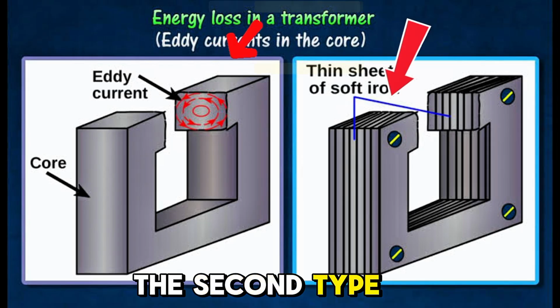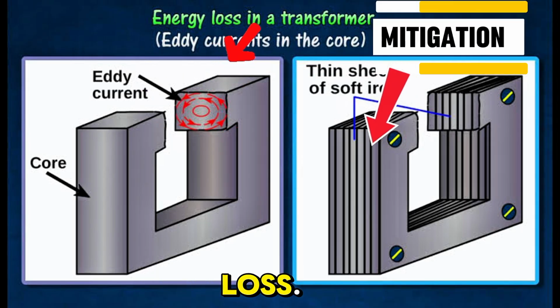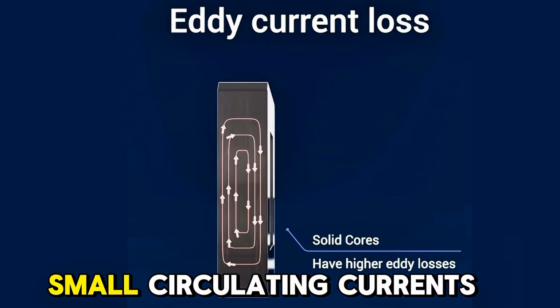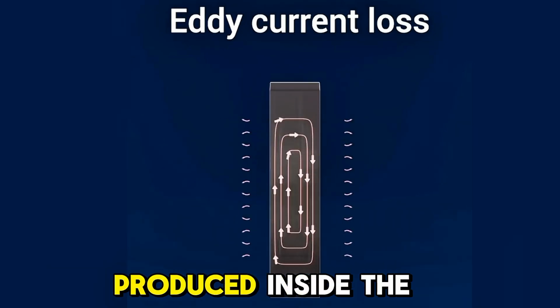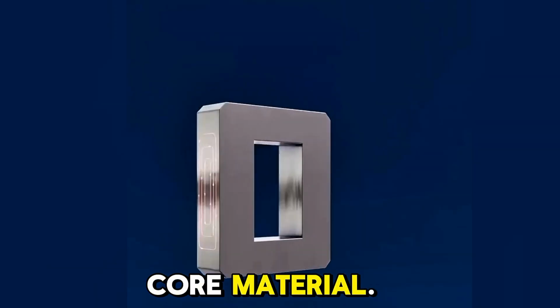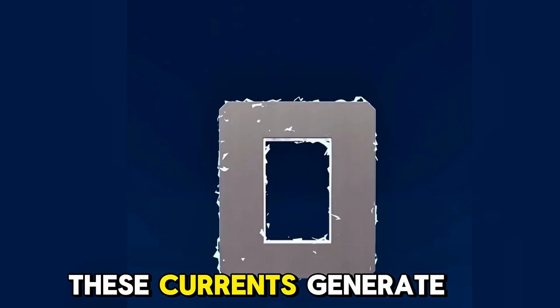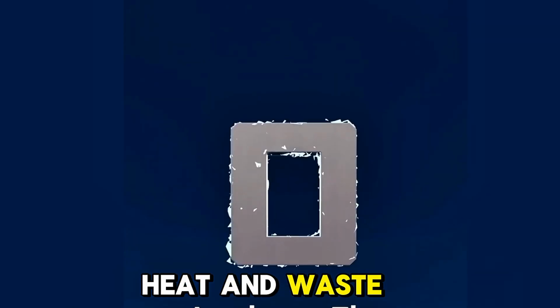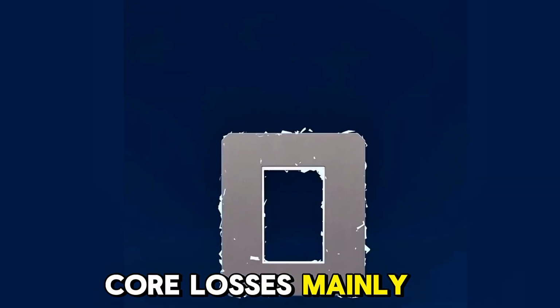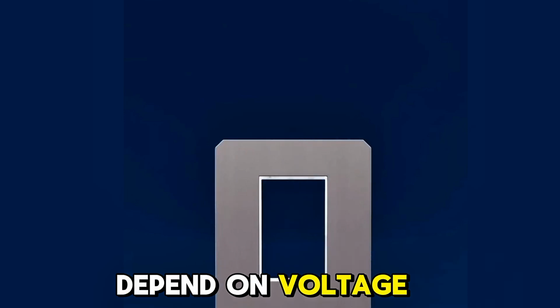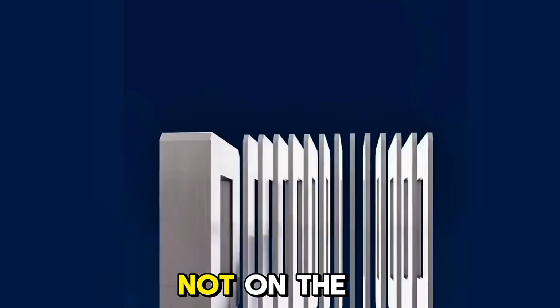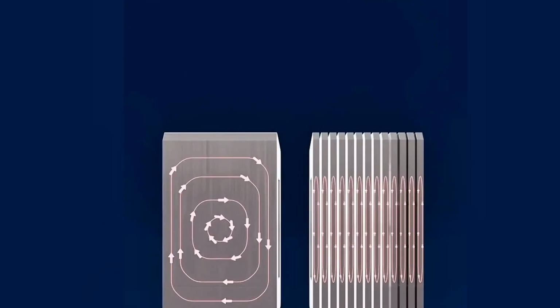The second type is eddy current loss. Eddy currents are small circulating currents produced inside the core material. These currents generate heat and waste energy. Core losses mainly depend on voltage and frequency, not on the load.